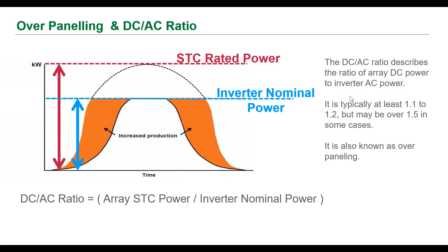Like instead of this 11:30, this will become 10:30. So I can increase my maximum production duration. That's what a higher DC-AC ratio does. People normally do that, but I can't over-design, because I need a break-even or trade-off where I will get the maximum yield. I can put 20 kilowatts on a 10 kilowatt system so that I will get a flat curve always. No, that is not the case. Then your capital investment will be more and the return on investment will be very, very less.